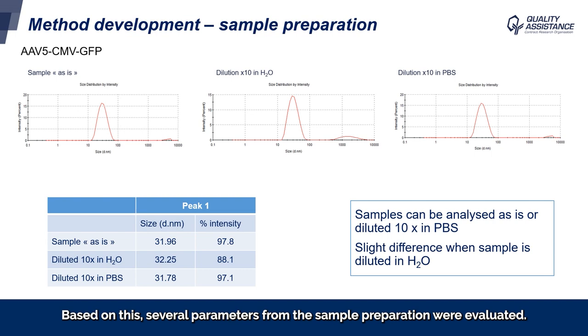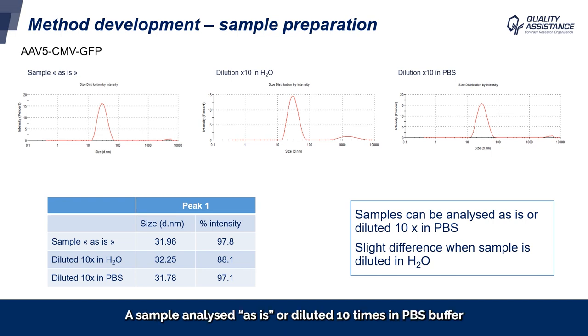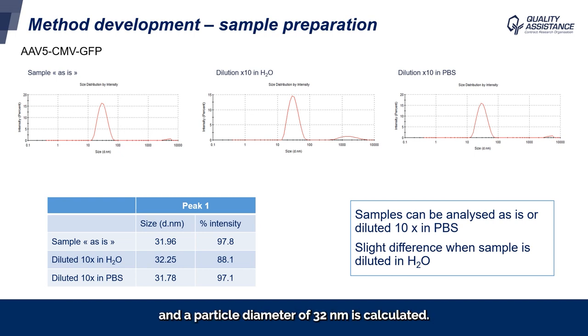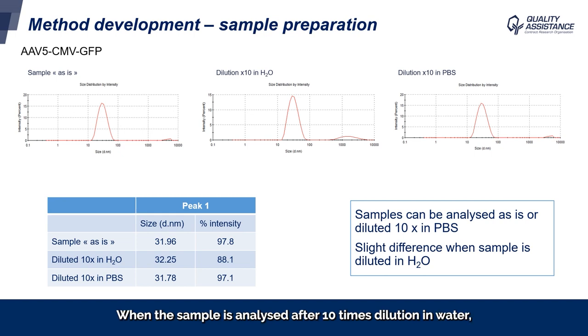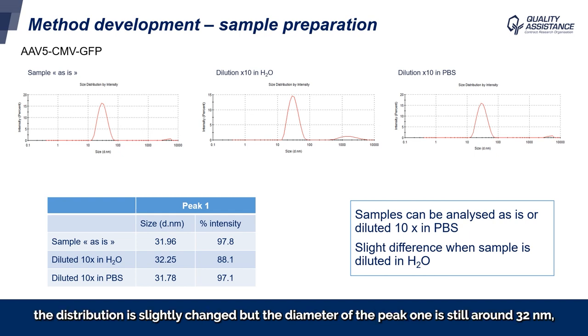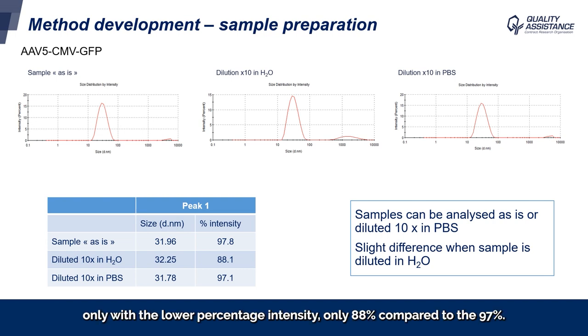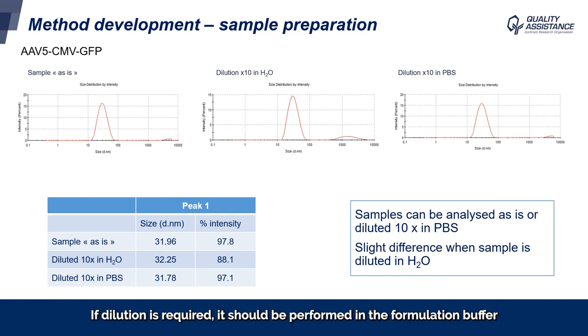Based on this, several parameters from the sample preparation were evaluated. We first checked the influence of dilution on the signal and the type of diluent. A sample analyzed as is, or diluted 10 times in PBS buffer, results in the same size distribution by intensity, with a particle diameter of 32 nanometers calculated. When the sample is analyzed after 10-times dilution in water, the distribution is slightly changed, but the diameter of peak one is still around 32 nanometers, only with a lower percentage intensity of 88% compared to 97%. Based on this, it was decided to analyze the samples as is. If dilution is required, it should be performed in the formulation buffer to avoid any changes to the aggregation status.